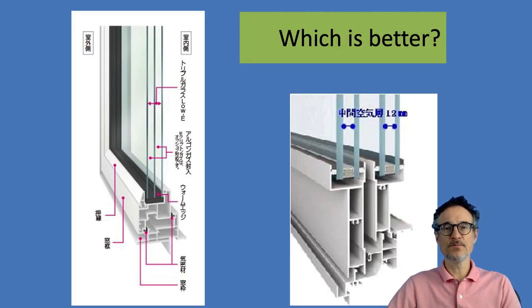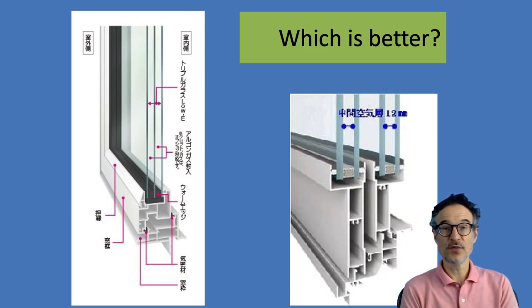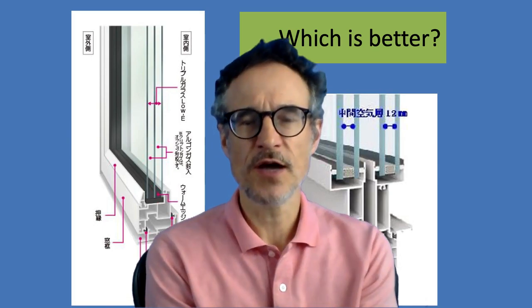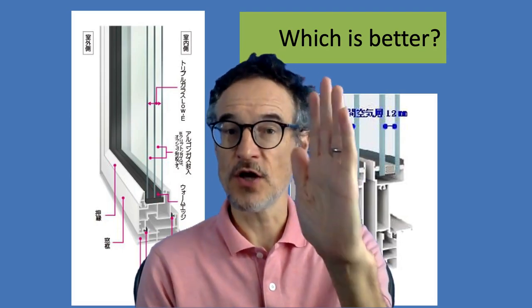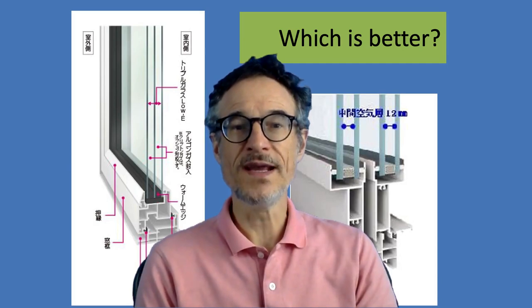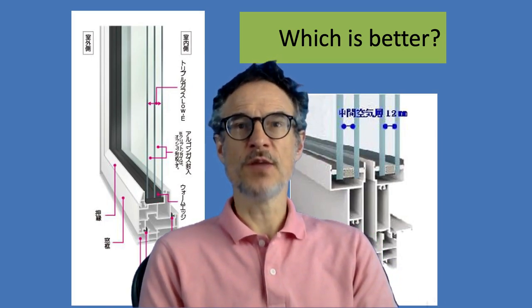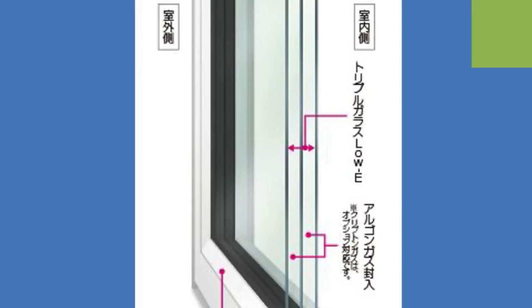Here are a couple of pictures of windows — which do you think is better? The one on the right, at first sight you may think that's four panes, that must be good. But in fact the window's open — it's actually two double-pane windows. If you look at how thin the frame is, that should be a bit worrying. What's likely happened is they've taken a standard single-pane window frame and just put another layer of glass on. This may help for the glass, but remember the frame is the weak link — that's where the heat goes, especially if it's aluminium. The window on the left is a triple-pane window and they've clearly thought about various other things.